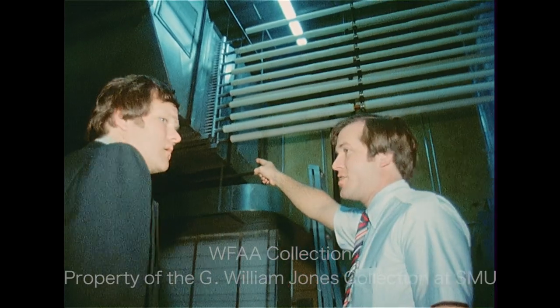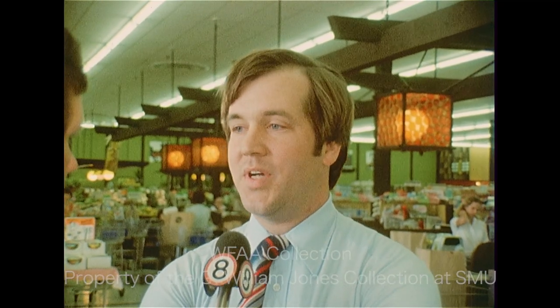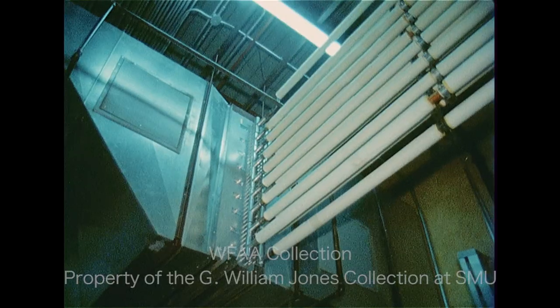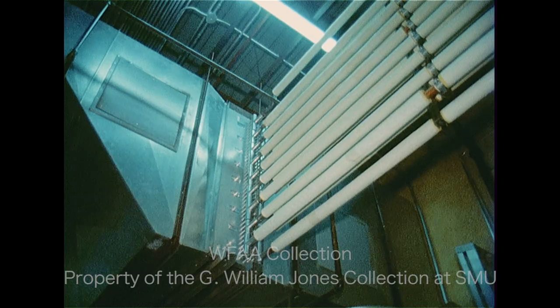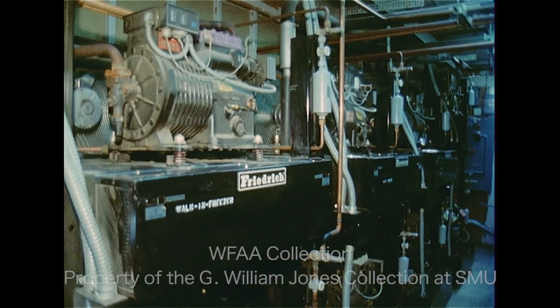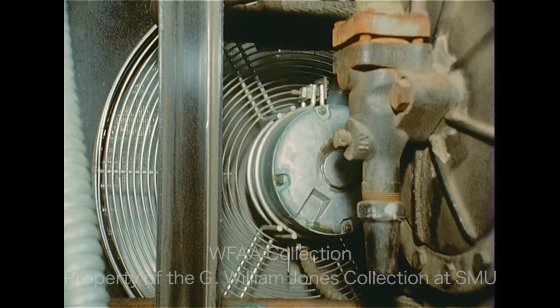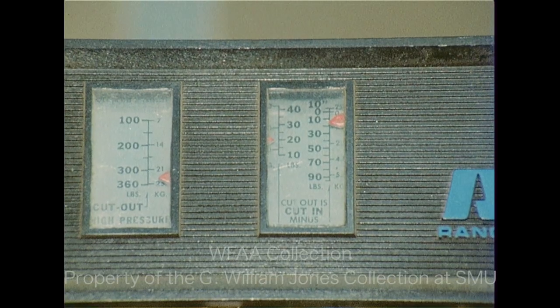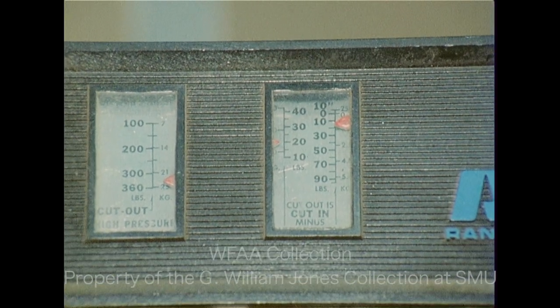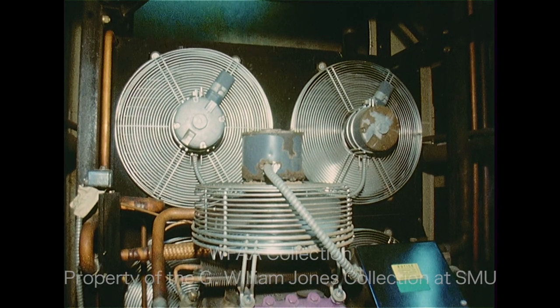But most significantly, many stores are now recycling their heat energy. Just like your air conditioner at home — you go outside, you feel heat coming off the unit that sits outside the house. That same heat comes off our refrigerated equipment. We recapture the heat and put it back into the store and use it for heating. Because of the refrigeration that we have in the store — the cases and the coolers, etc. — heat is required longer in our stores than it is in a home.